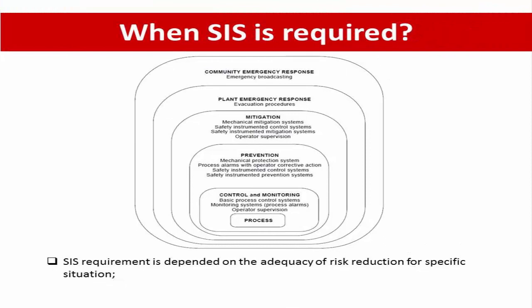When is SIS required? SIS requirements depend on the adequacy of risk reduction for specific situations. The main concept of necessary risk reduction is the reduction in risk that has to be achieved to meet the tolerable risk or process safety target level for a specific situation. The necessary risk reduction may be achieved by either a Safety Instrumented System, other protection layers, or even a person as an integral part of the safety function. For example, an operator can be alerted by a process alarm and perform a safety action based on that.